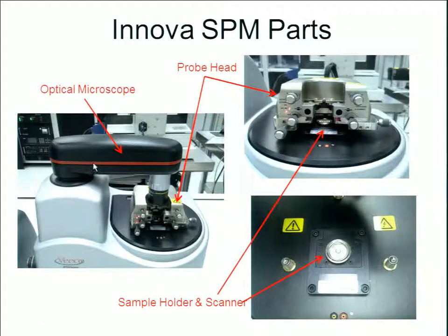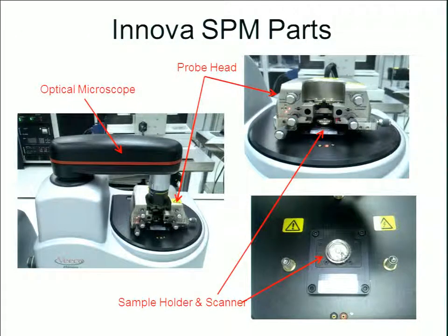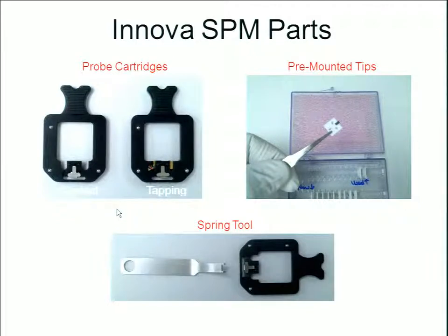Looking more closely at the instrument, we see the optical microscope. Below this is the probe head, which will hold our cantilever and tip. Below the probe head is the top of our piezoelectric scanner, and just above that is a magnetized metal plate for holding our samples. If you've wondered how you hold a cantilever that's so small — with a tip that goes down to 20 nanometers — one way is that they come packaged on a tiny chip of silicon.